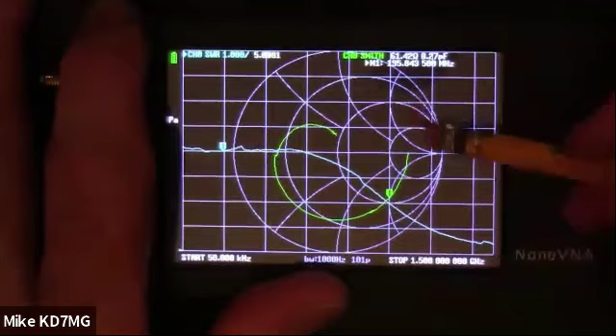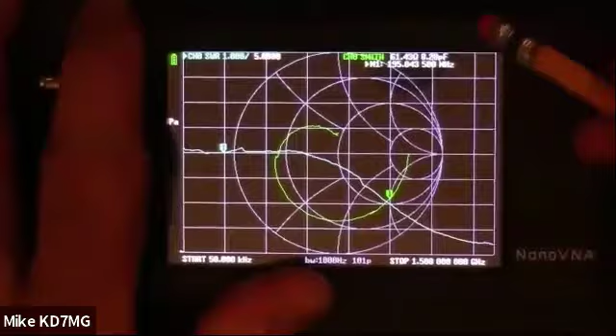Okay. The thing you need to do when you first get the unit is do what's called a user calibration. This is different than a full-on calibration by the factory, but even modern-day VNAs have to go through a user calibration. So before we do that, let's set up our stimulus. There. That's the signal generator inside. We want to set a start of 50 kilohertz, which is the bottom end, and a stop of 1.5 gigahertz at the top end. I think it was there already, but anyway, that's how you set the start and stop frequencies.